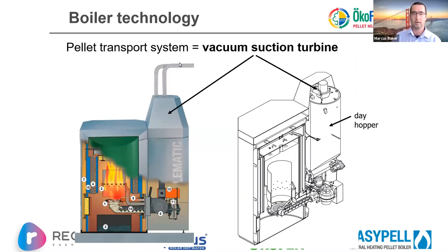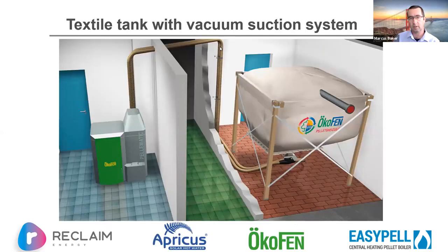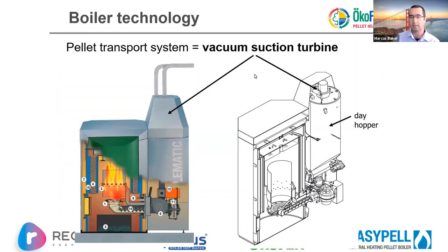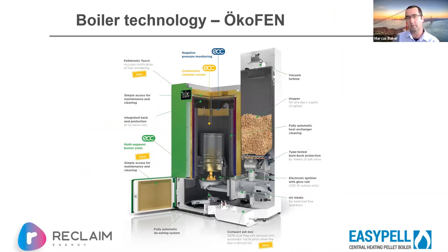The easiest way to move pellets from storage is by a vacuum system, and the majority of companies now supply their boilers with one as standard. 'Vacuum' is a slight misnomer — you've actually got a fan that blows air across the end of the pellet store outlet, drawing pellets out of the container and blowing them through to the boiler where they fall into the day hopper.